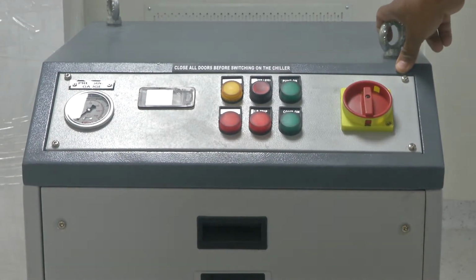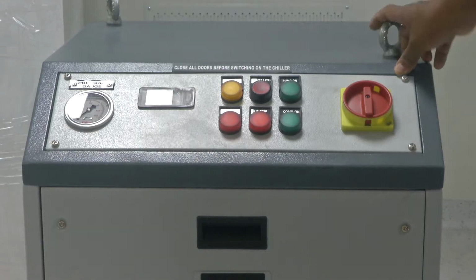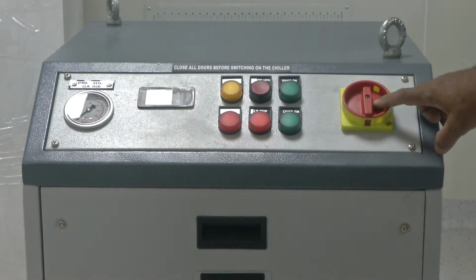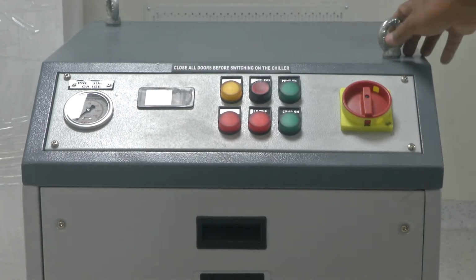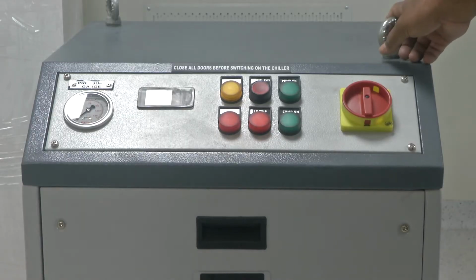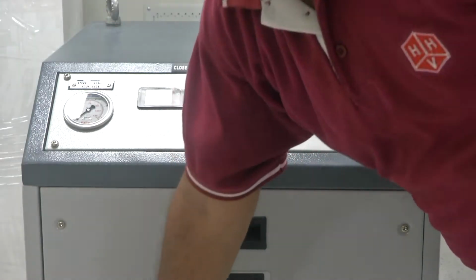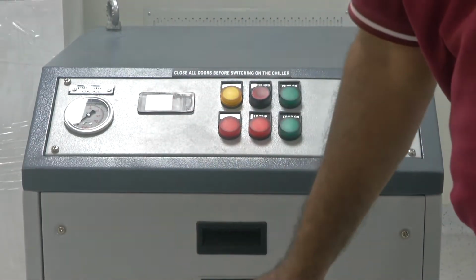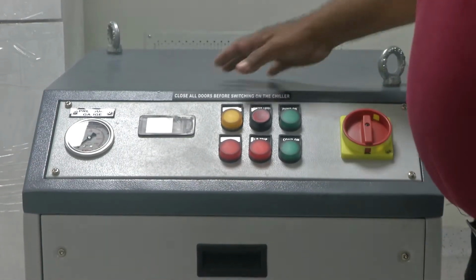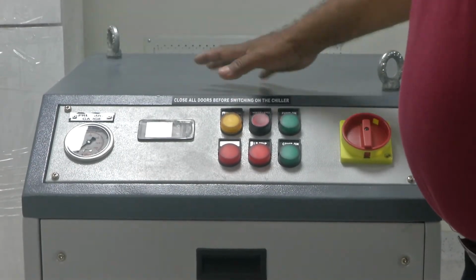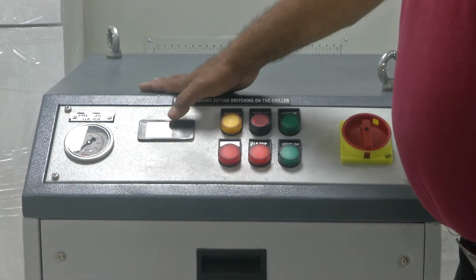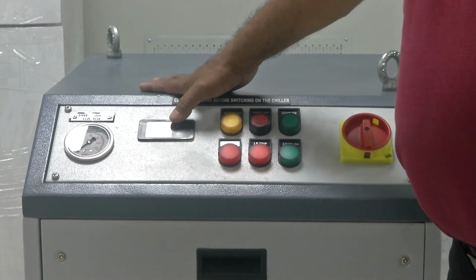this is the chiller unit make. This is the main power supply, main circuit breaker, and fill the DM water. And this is the water level. This should be maximum level. This is power main. Switch on main. This is a temperature indication. You can vary whatever the required temperature.